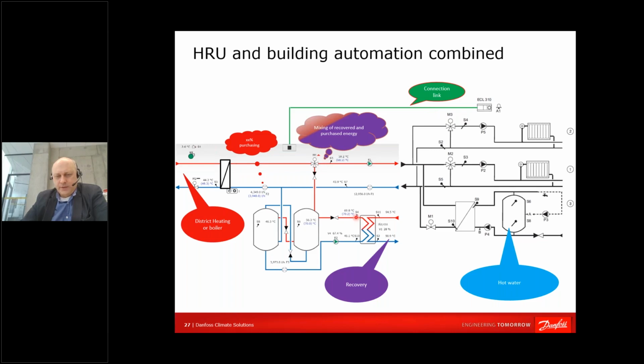And here you can see additionally 4 sensors. These 2 on the return are used to keep the heat exchanger from stress. So we are not pumping fast, because we are utilizing a PWM modulation control algorithm, and we are not running the pump with a start-stop algorithm. We are gradually increasing and decreasing the speed of the pump, and we are keeping balance here. And of course, we are monitoring temperatures on the supply side. So that's how it works.